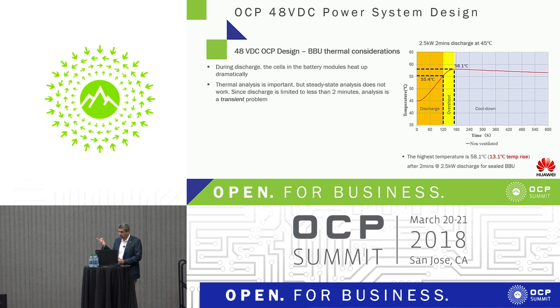So this is an actual test result. We're starting at 45 degrees C, so you're already really, really hot in your data center. We go through the discharge, rapid heat up of the batteries, obviously, because they're dumping all their energy. They've got 2 minutes to dump all their energy. Then we stop at 120 seconds, 2 minutes, we stop the discharge, and the batteries continue to heat up, because they've built up all this energy, and now the heat is conducting its way out from the center of the cells out to the environment. Then it takes a while for them to go through the cool down.